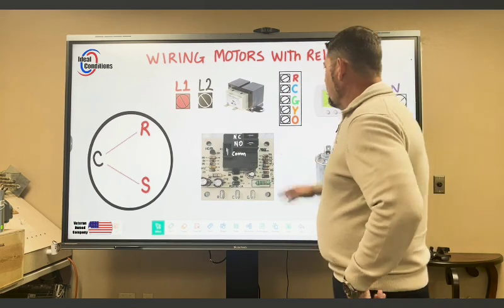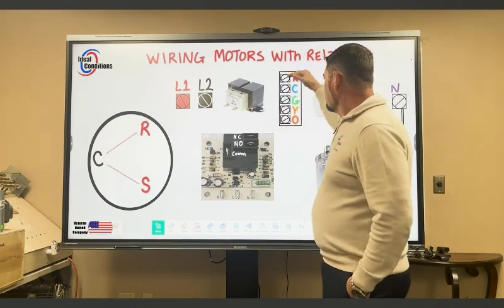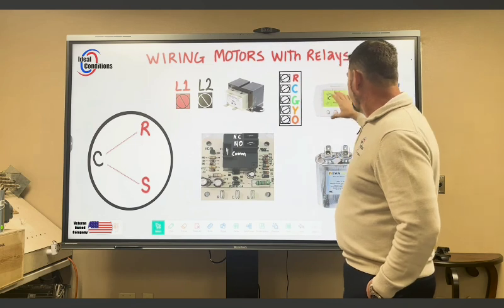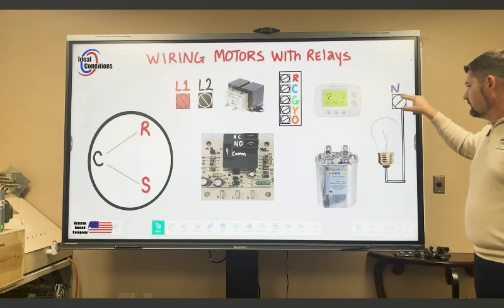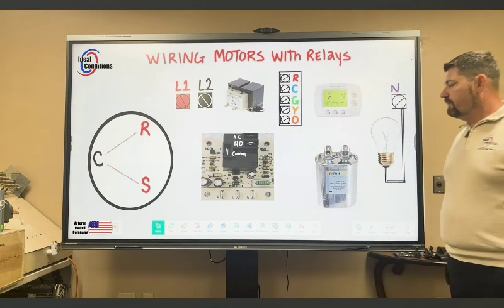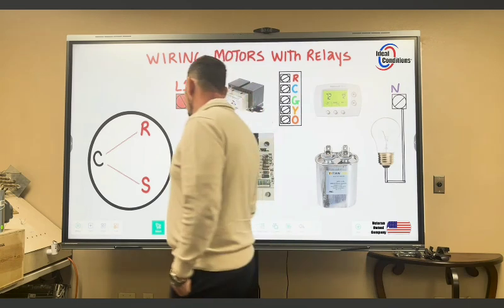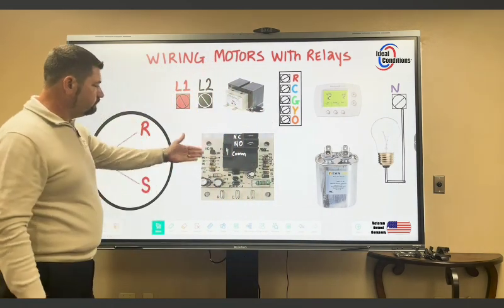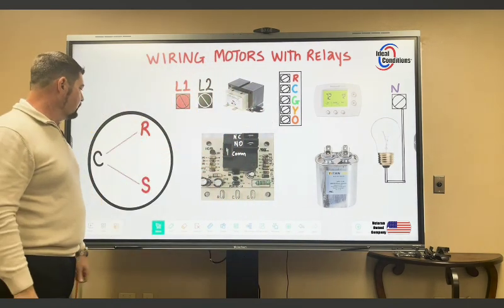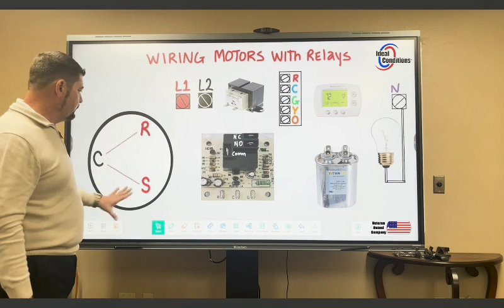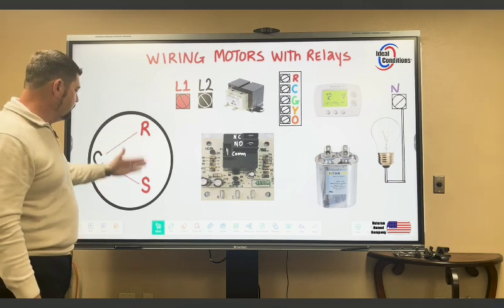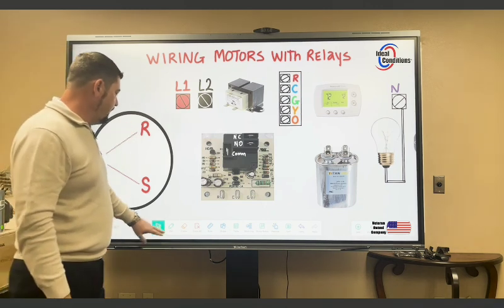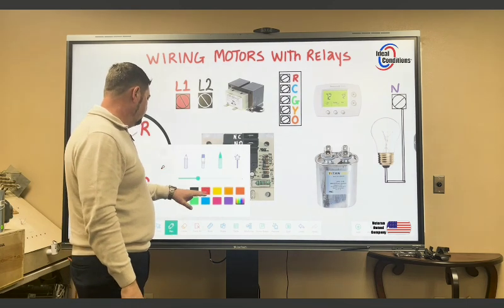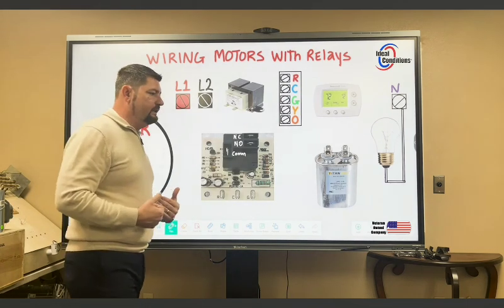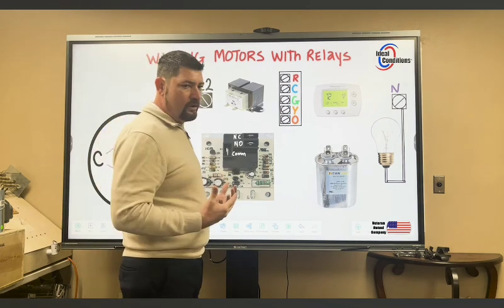All right, we have L1 and L2, a transformer, a low voltage terminal block, a thermostat. We have our light bulb up here giving us a neutral. We have a run capacitor, the ICM 255 blower control board, and we have a diagram of our motor windings: run, start, and common. We're going to go ahead and get right into it. First thing we're going to talk about is safety. That safety that you need to keep in mind is imperative.